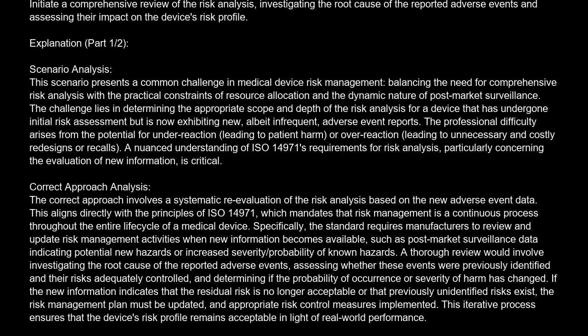Correct approach analysis. The correct approach involves a systematic re-evaluation of the risk analysis based on the new adverse event data. This aligns directly with the principles of ISO 14971, which mandates that risk management is a continuous process throughout the entire life cycle of a medical device. Specifically, the standard requires manufacturers to review and update risk management activities when new information becomes available, such as post-market surveillance data indicating potential new hazards or increased severity/probability of known hazards.